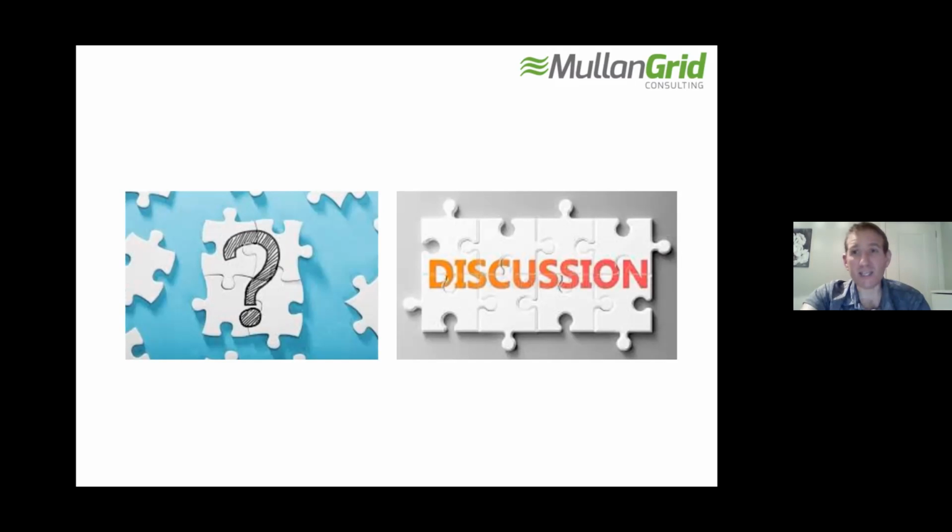Well, what people are probably doing is, the easiest way of getting an on-site generator connected is to go zero export. But then once you've got it zero export, the next thing is, there are times maybe you're not using the power, so then you probably should try to get an export agreement. Now, there might be export capacity. So before you actually build your project, you need to make sure you're not dependent on that export capacity. But if you're not dependent on it, it probably does make sense to do it in 2 steps. Get it built under zero export and then apply for export capacity.